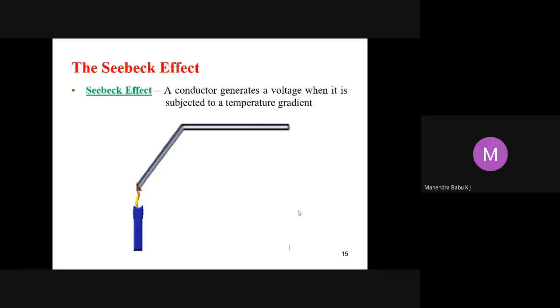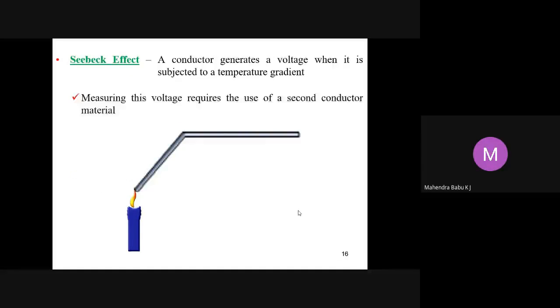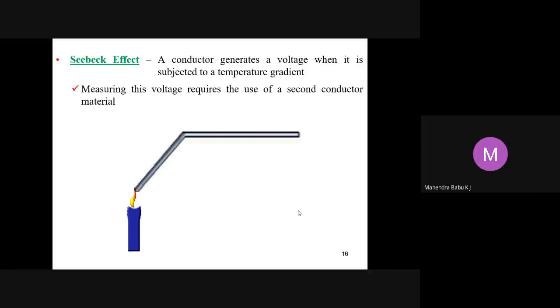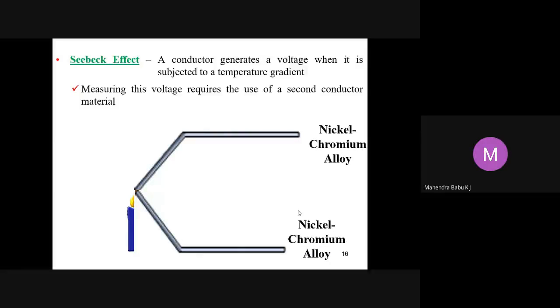Temperature gradient. Measuring this voltage requires the use of a second conductor material. With a single conductor, we can't measure the voltage. We need a second conductor. Suppose you use a second conductor of nickel chromium alloy, so both are of the same material.